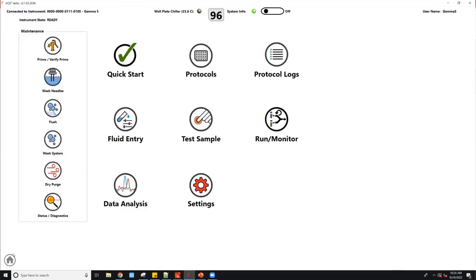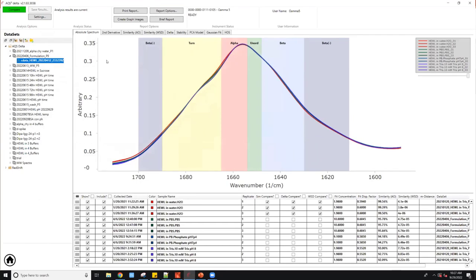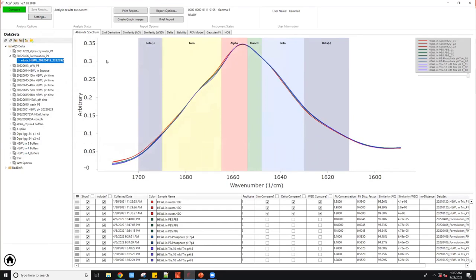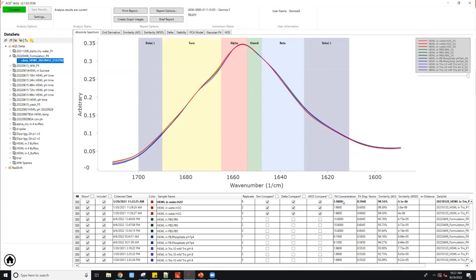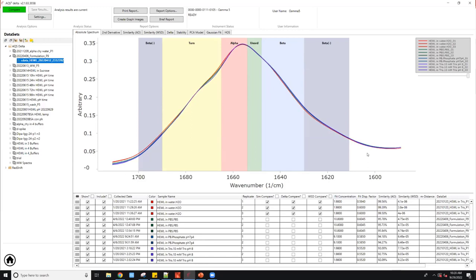Let's just imagine that eight hours have passed and all the data has been collected. Let's come over to this data analysis window. Once the data is analyzed, this is the window that you're gonna see. There are a lot of tabs that just go through them one by one. The first one is the absolute spectrum, which is when you interpolate all the raw data points into a spectrum. And what we also do here is to normalize the concentration. As you can see in this table here, we have the fit concentration. MMS can quantify the real concentration of your biomolecule in your sample by fitting it. Here we have like 2 mg/mL and 10, and it's normalized so they are all kind of overlaid with each other.